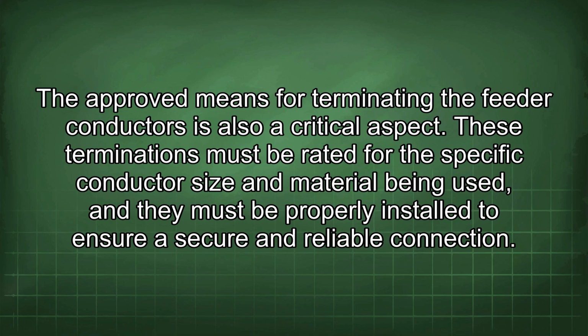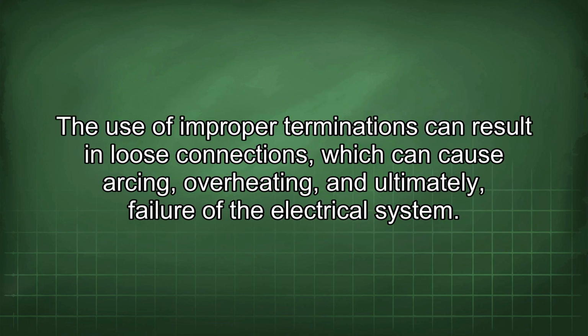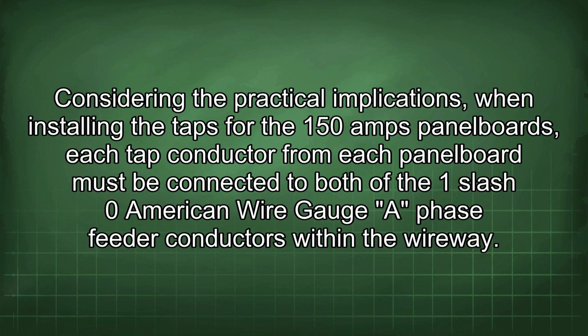The approved means for terminating the feeder conductors is also a critical aspect. These terminations must be rated for the specific conductor size and material being used, and they must be properly installed to ensure a secure and reliable connection. The use of improper terminations can result in loose connections, which can cause arcing, overheating, and ultimately, failure of the electrical system. Considering the practical implications when installing the taps for the 150 amp panel boards, each tap conductor from each panel board must be connected to both of the 1/0 American wire gauge phase feeder conductors within the wireway.